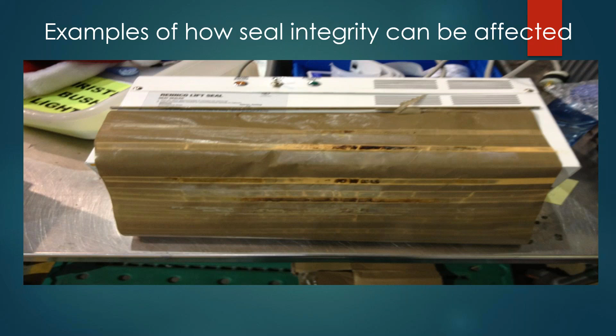I love when someone can come up with something that takes something that could be considered subjective and make it objective. And I love this seal integrity test because it can actually test the lot number of a set of peel packs, checking the seal made by the manufacturer. Then it can test the seal itself created by the peel pack machine. And it can be used as a competency device as well. You could have people seal this in and see how well they're doing. And this is just a great, quick, easy visual way to do that.